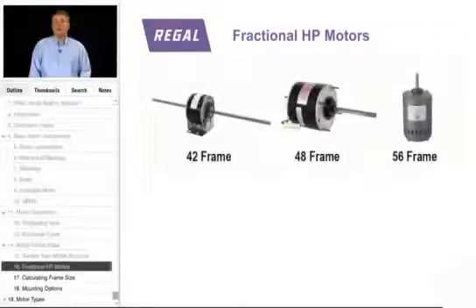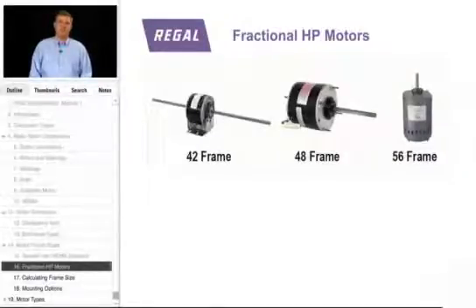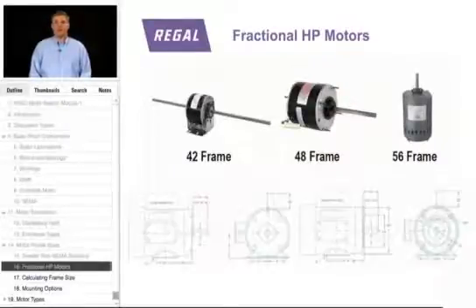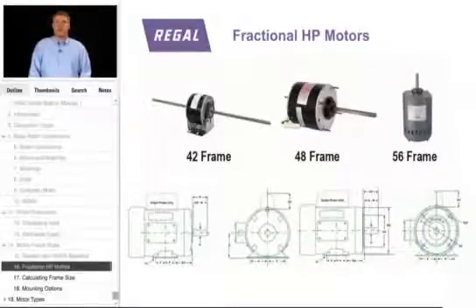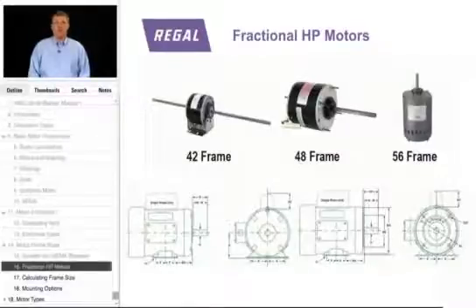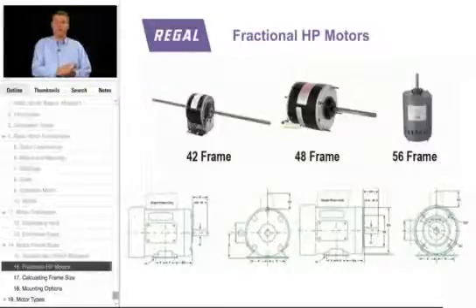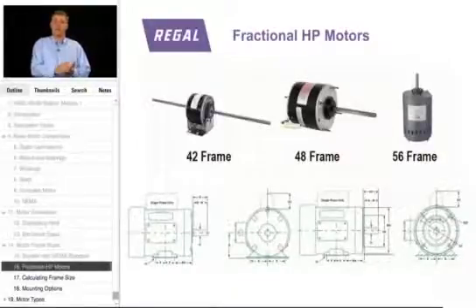The next group of motors in frame size is 42, 48, and 56 frame motors, which we refer to in the industry as fractional horsepower or FHP motors. For 42, 48, and 56 frame motors, the frame size truly tells us where the center of shaft is in an application — so that when I take a motor out and put a motor back in, the center of shaft is in the same spot, ensuring the wheel, blade, or whatever is driven doesn't hit the side of the housing.